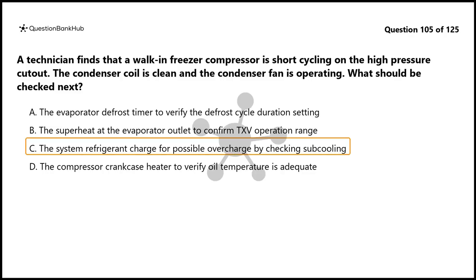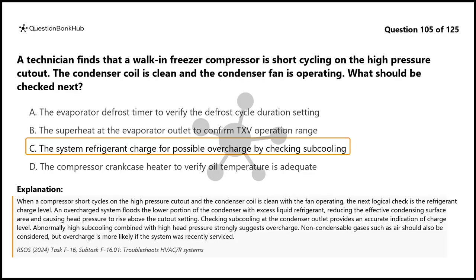The correct answer is C. When a compressor short cycles on the high-pressure cutout and the condenser coil is clean with the fan operating, the next logical check is the refrigerant charge level. An overcharged system floods the lower portion of the condenser with excess liquid refrigerant, reducing the effective condensing surface area and causing head pressure to rise above the cutout setting.